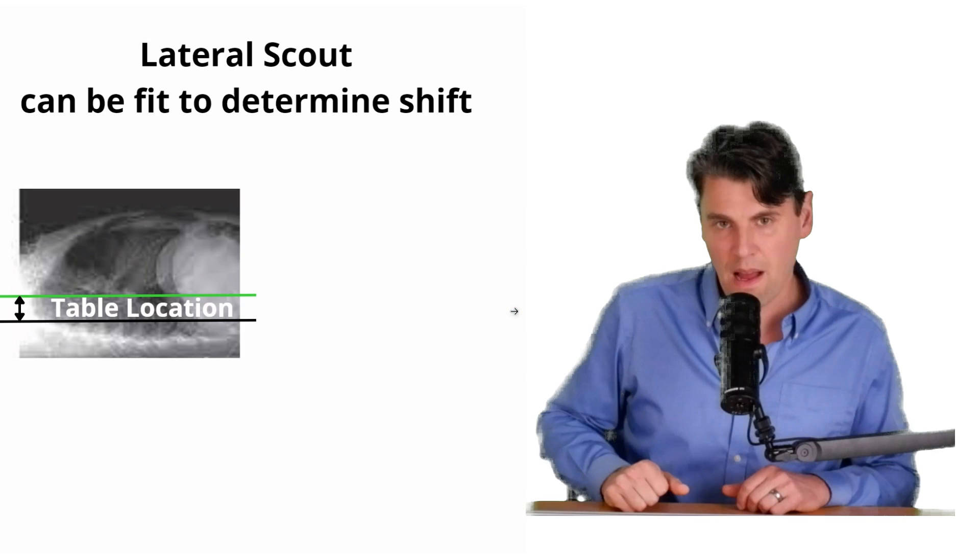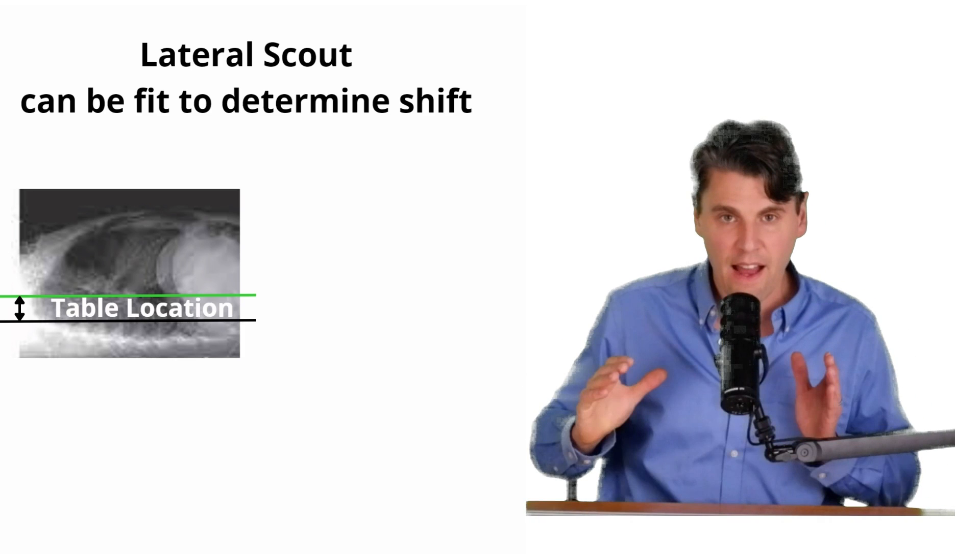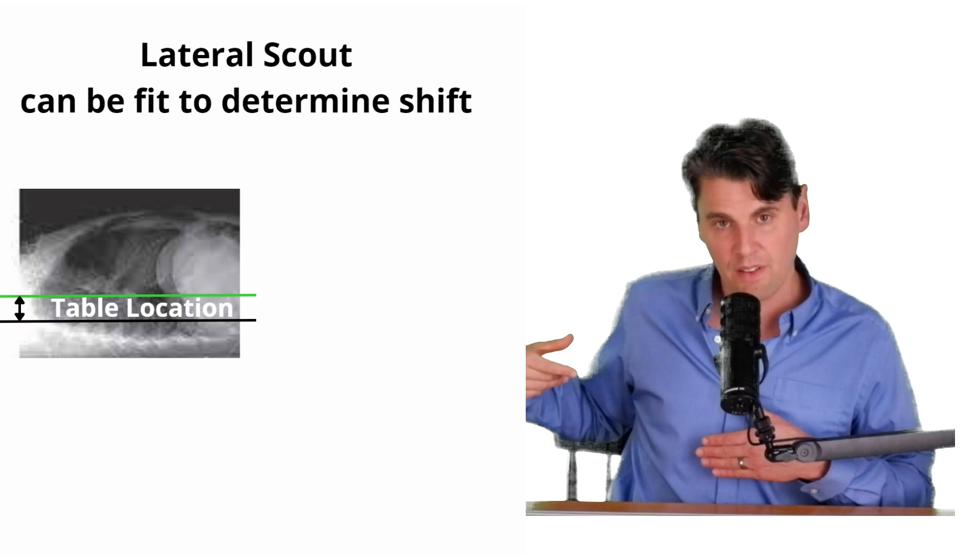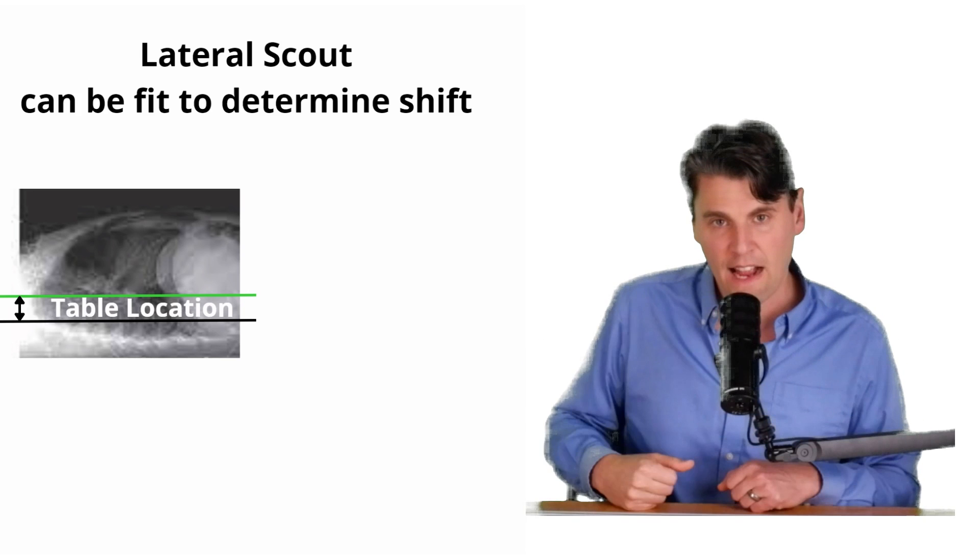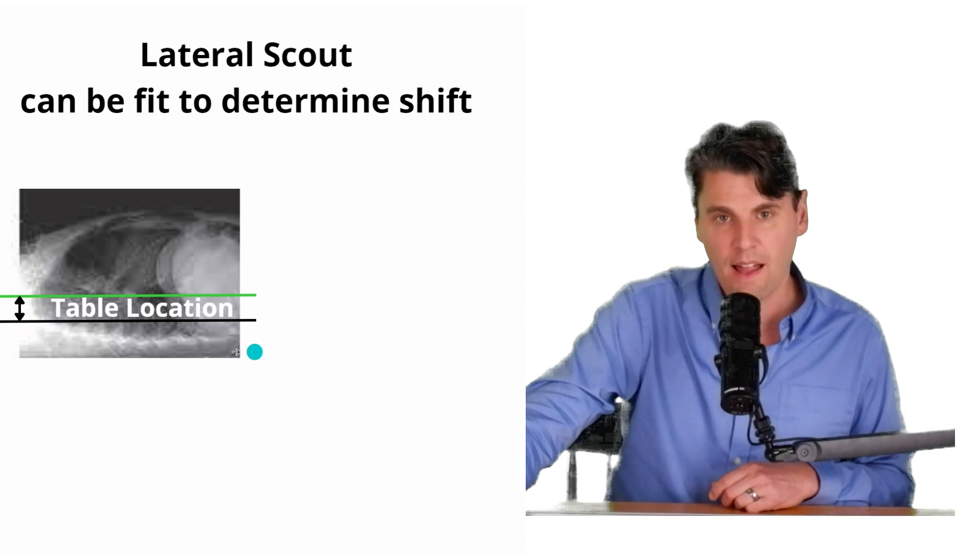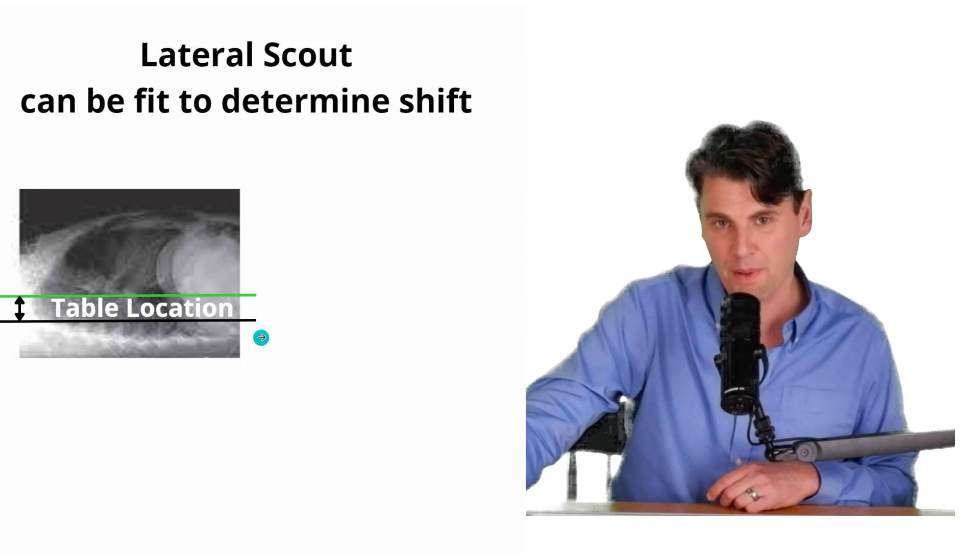So what can you do about this? If you actually look at the lateral scout, you can tell if you're too high or too low based on measurements that you can do in the scout. So now the vendors actually have this as an option on the scanner, where there will be a line on the scanner indicating where the center is and where you want it to be.